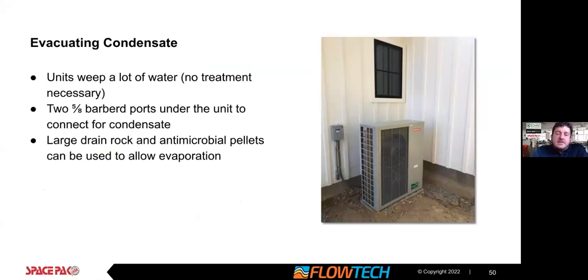Evacuating condensate. This is a SIM unit. This is one of our beta tests, and there's two little barbed ports under the unit, so it can be used to get a condensate drain out. Some contractors will put a decorative drain rock around it, like a kind of a box of decorative drain rock, so the condensate can get in there and have time to evaporate. But just something to consider, especially if it's in a public area with a walkway, that it's a good idea to take care of that condensate.